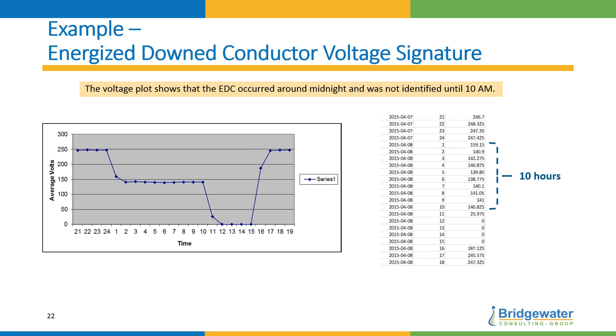Another use case that we have is the outage footprint identification. Now, at a couple of utilities we were getting PONs, power outage notifications, but only a portion of them were coming in, and a little bit later. We were still relying on phone calls to do the major portion of the analytics in OMS.